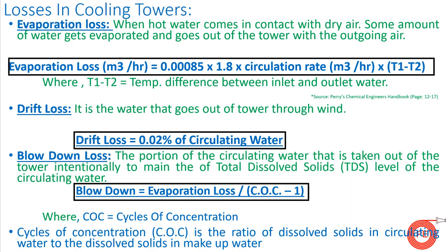Now let's look at the different losses in cooling towers. Water is precious and governments have strict norms on its usage. The first loss is evaporation loss — when hot water comes in contact with dry air, some water evaporates into the atmosphere. The empirical formula is: Evaporation Loss = 0.00085 × 1.8 × Circulation Rate × (T1 − T2), where T1 and T2 are the inlet and outlet water temperatures.